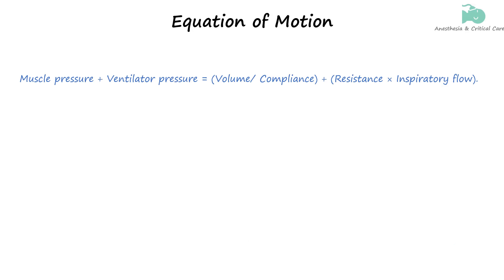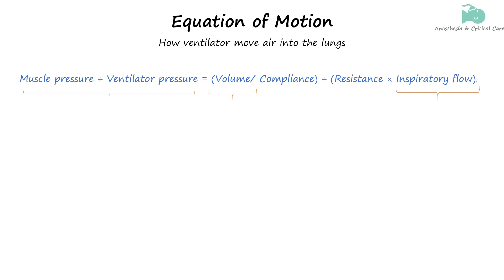Before we begin with control variables, let's briefly go over the mathematical model that relates pressure, volume, and flow during ventilation. This model is known as the equation of the dynamics of the respiratory apparatus, or the equation of motion. It describes how the ventilator moves air into the lungs — specifically, the amount of pressure required to drive air into the lungs at a certain flow rate to achieve a required tidal volume, based on the respiratory compliance and resistance of the patient's lungs.